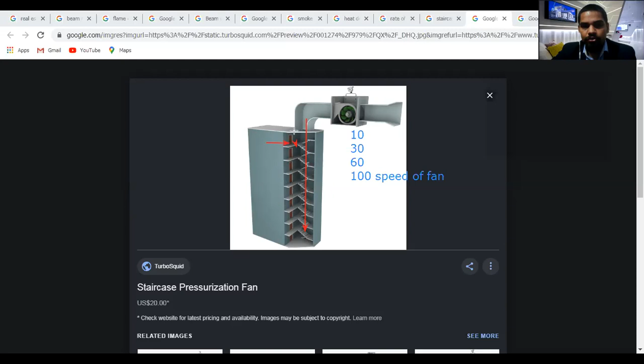But when the fire happens and you have started the fire panel staircase pressurization at 100% speed, it also creates a drawback: normal people will not be able to open the door and will not be able to access the staircase. So it depends on how many floors are affected, and what speed we have to run.